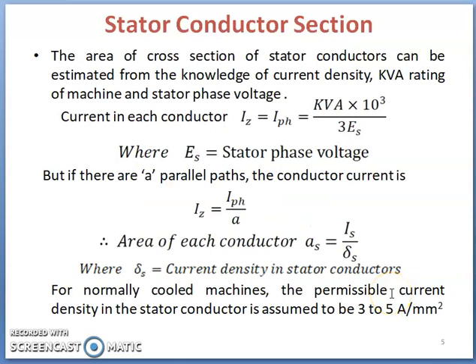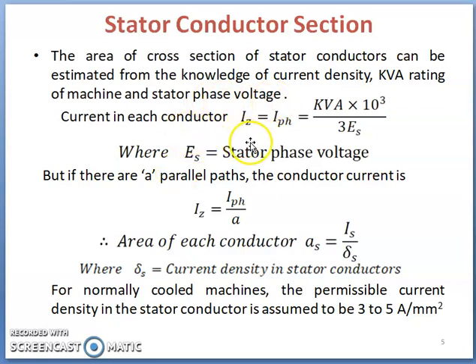To find the cross-sectional area of each conductor, the stator current as well as current density in the stator conductor should be known. The area of cross-section of stator conductors can be estimated from knowledge of current density, kVA rating of the machine, and stator phase voltage. Current in each conductor Iz equals Iph, which equals Q (kVA rating) times 10 to the power of 3 divided by 3*Es, since Q equals 3 * Es * Iph.